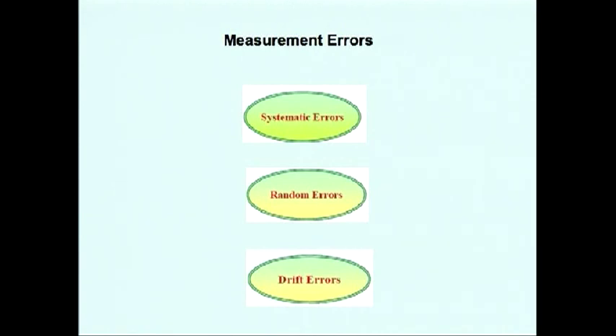Systematic errors are repeatable and are assumed to be time-invariant. They can be characterized during the calibration process and mathematically reduced during measurements. They are never completely removed though. There are always some residual errors due to limitations in the calibration process. The residual systematic errors result from imperfections in the calibration standards, connector interface, interconnecting cables, and instrumentation.